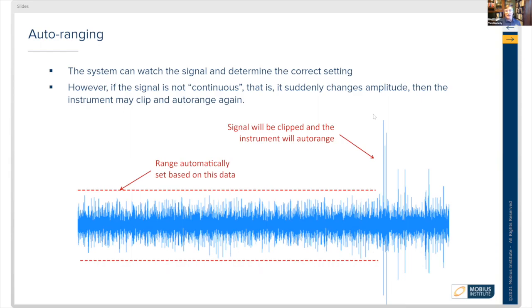On the left side through the middle of this time waveform, the range is automatically set based on the data being captured. But towards the end, there were big impacts or something that generated additional sound. That signal will be clipped and the instrument will auto-range again. You have to take good long data series to ensure the auto-ranging adjusts to any new peaks.